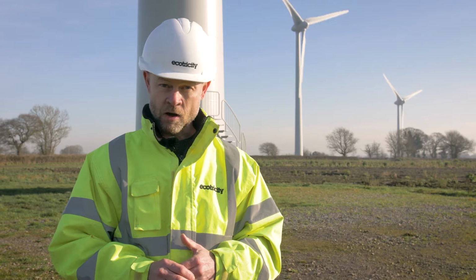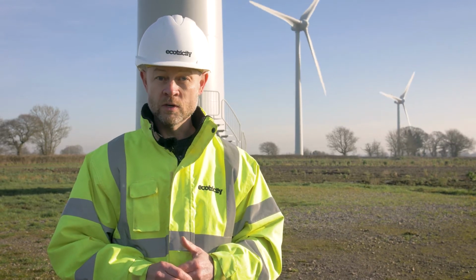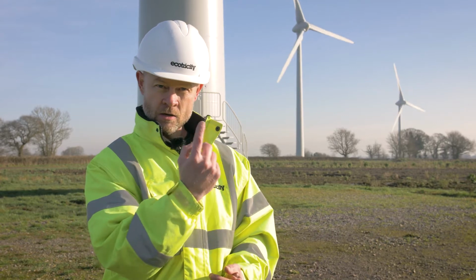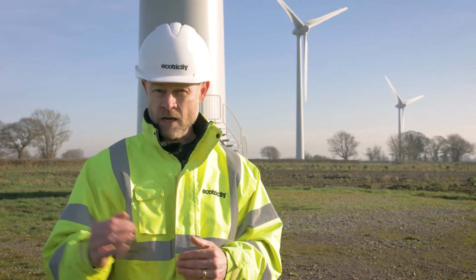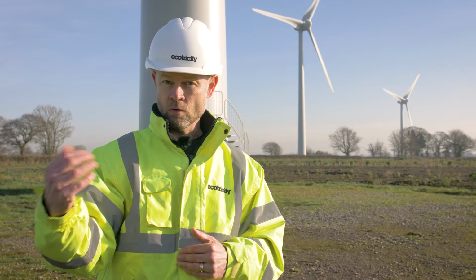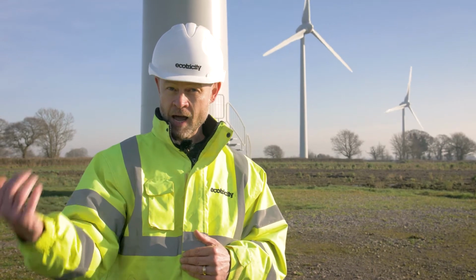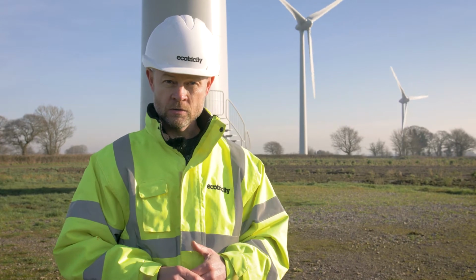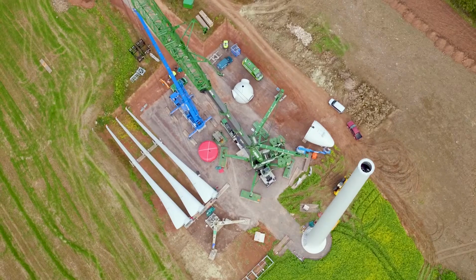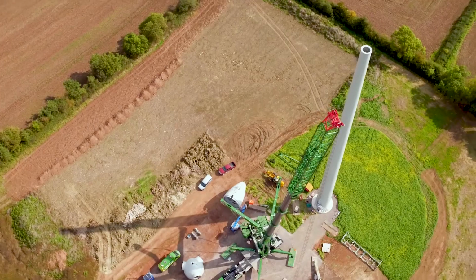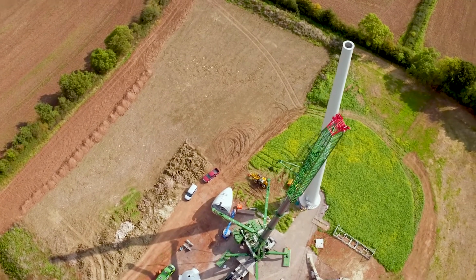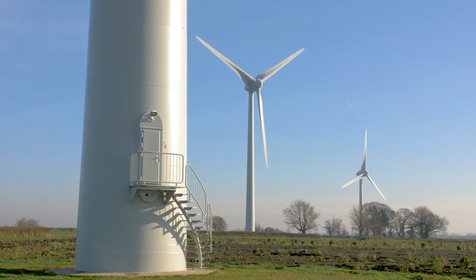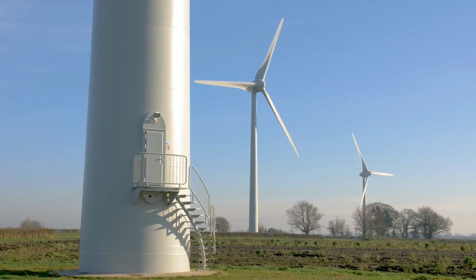Another factor from a time point of view is we need to know what the wind resource is. So we put a monitoring mast up which has anemometers at various heights, and that tells us what the wind speed is doing, what the direction of the wind is doing, and how much wind we can gather with our particular windmills once we put the final design in. That also tells us what height we would like to build those to get the maximum amount of wind from them. So putting all those factors together, for this particular site, we ended up with 3.